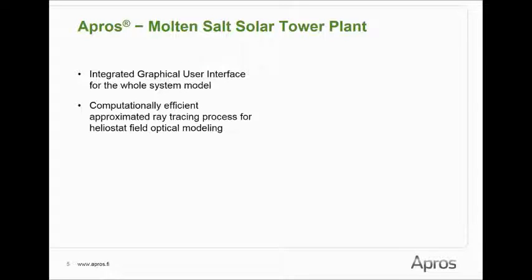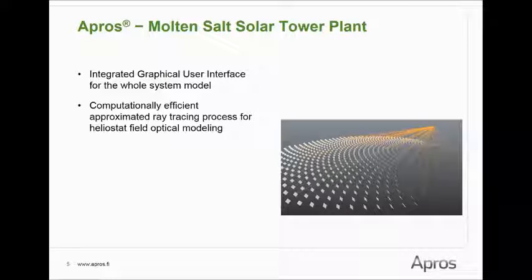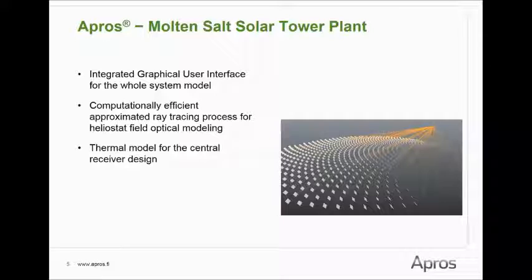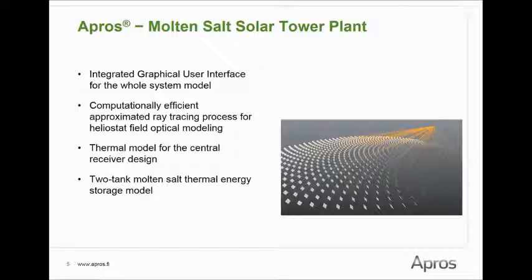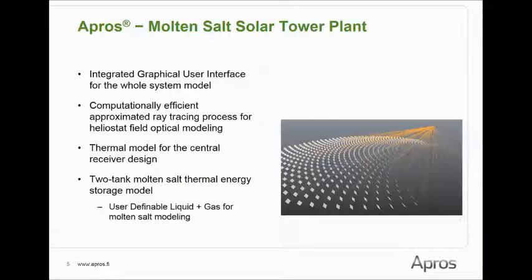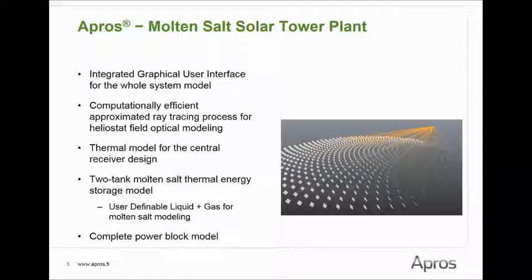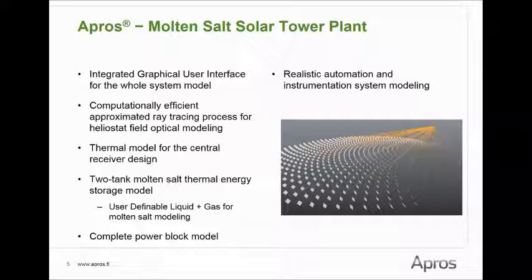The model includes a computationally efficient, approximated ray tracing process for heliostat field optical modeling, a thermal model for the central receiver, a two-tank molten salt thermal energy storage system, a complete power block model, and a realistic automation and instrumentation system. The molten salt fluid model is an example of an extendable user-definable liquid and gas mechanism of APROS.